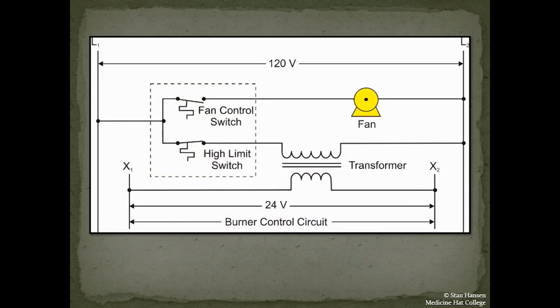And for any unit that uses a combination control that has both the fan control and the high limit in it, I need to be aware of the voltages for each of these systems. Canadian Electrical Code says I cannot mix my 120 volt circuit with my 24 volt circuit within the same device. Since my fan control is a 120 volt power circuit, and my high limit operates my ignition circuit, which is lower voltage, I cannot have both those voltages in the same control. If I do have one control for both of those units, I'm going to use my high limit to control the transformer that powers my valve. That way, all the power that is inside that combination unit is 120 volts, and I'm not mixing any voltages.